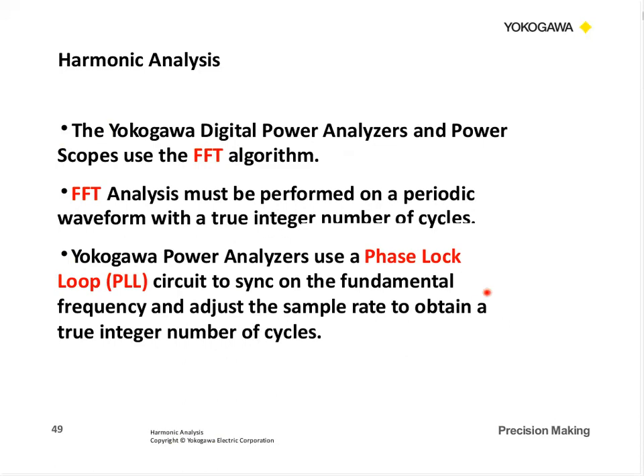So again, we use the FFT algorithm. And on the FFT, this is very important: the analysis must be performed on a periodic waveform with a true integer number of cycles. And this is very important. And to do that, in our power analyzers, we use a phase lock loop tuning circuit. You'll see PLL, phase lock loop.